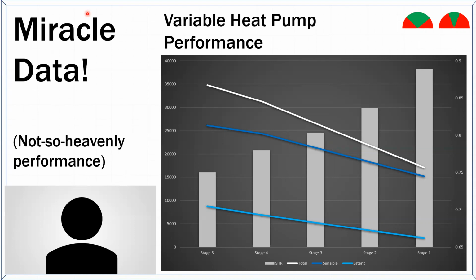Well, you're supposed to size off the high stage. But you've got people out here banging the drum saying the solution to all our problems is load matching - meaning as the load goes down, the capacity of the equipment goes down, because that's going to give you long run times. And yes, it will give you long run times, but will it give you the moisture removal needs, or meet the moisture removal needs of your home? That's a different question, because everybody's playing the damned SEER game.